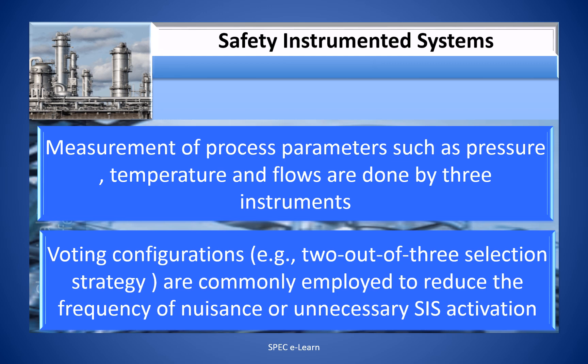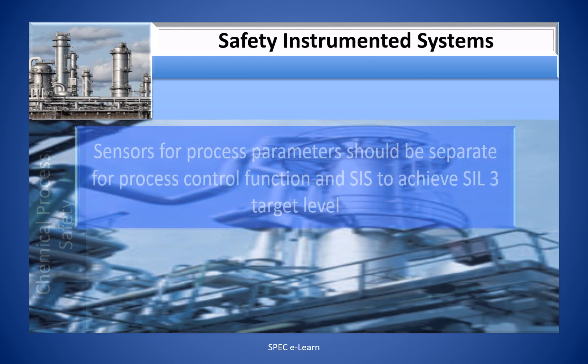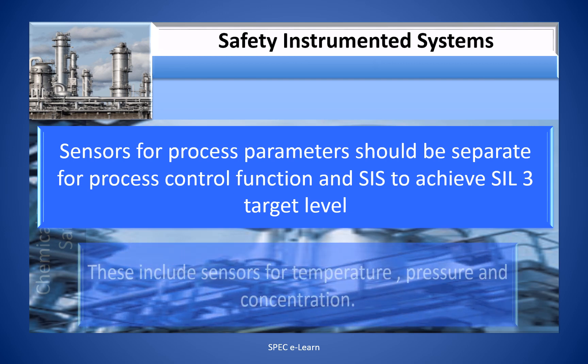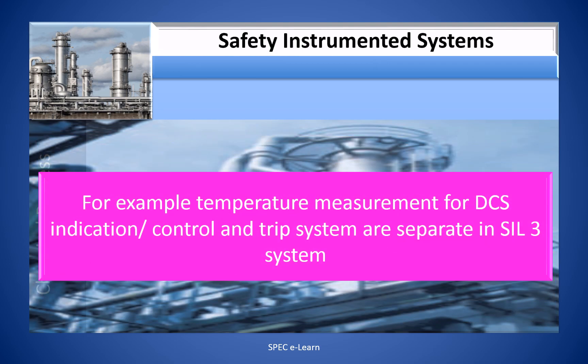Two-out-of-three selection strategies are commonly employed to reduce the frequency of unnecessary or nuisance SIS activations. Sensors for process parameters should be separate for process control functions and SIS to achieve the SIL 3 target level. This includes sensors for temperature, pressure, and concentration. For example, temperature transmitters for DCS indication or control and the TRIP system are separate in a SIL 3 system.